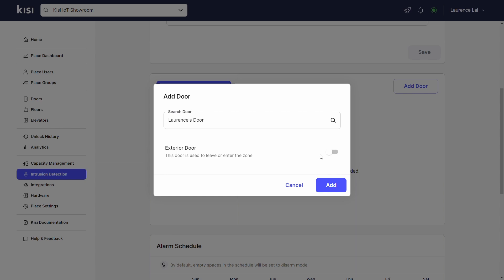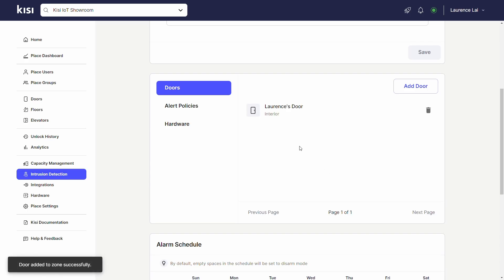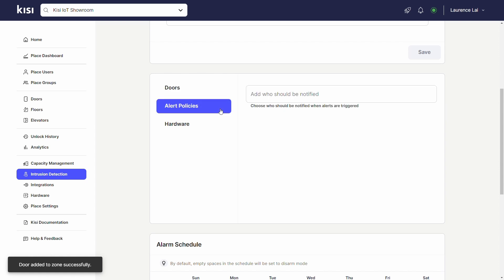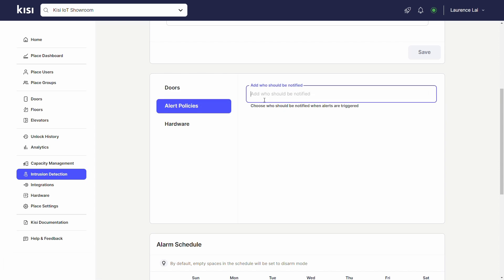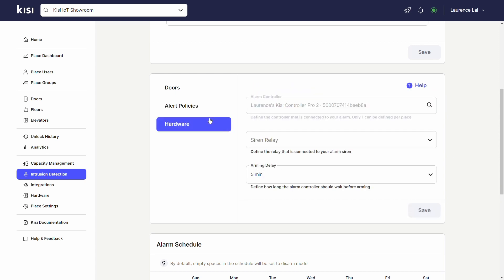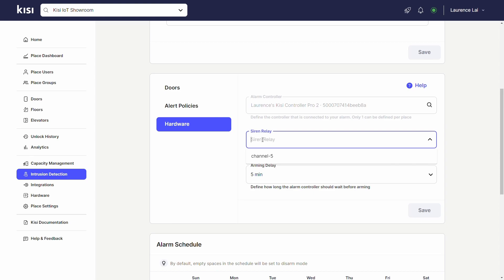You can enable the exterior door if the door is used to leave or enter the zone. Click on Alert Policies and type in the email of anyone you want this Intrusion Detection Zone to notify. Click on Hardware to wire the siren. Under Siren Relay, select the relay the siren alarm is wired to.